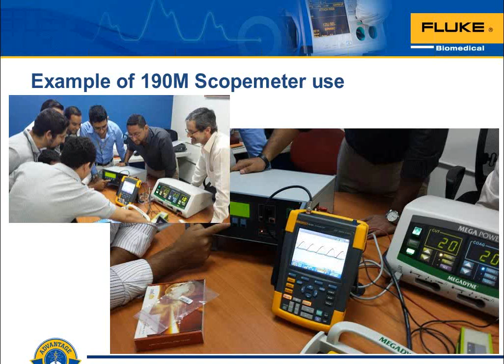Now, tip number 5. Be mindful of test leads while you're testing. Keep in mind that we're dealing with radio frequency energy here. High frequency behaves quite differently than low frequency energy. It radiates and induces electrical current flow in addition to any conductive current flow that's going through the test leads when those test leads cross or when those test leads are coiled. So you don't want your test leads to act like antennas, because I guarantee your measurement values are going to be affected one way or another. So make sure your test leads are draped properly and don't cross each other, and that there are no coils in your test leads. Keep the test lead as short as possible so that it makes it easier to do that. But the test leads are really important to getting this testing right.